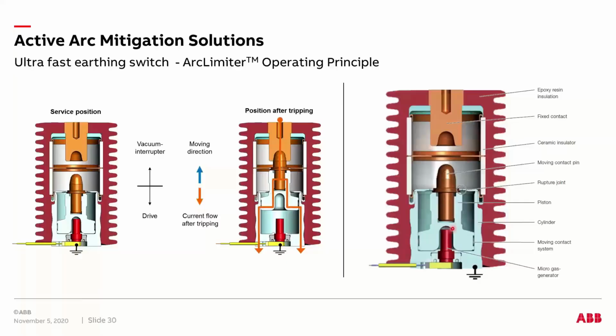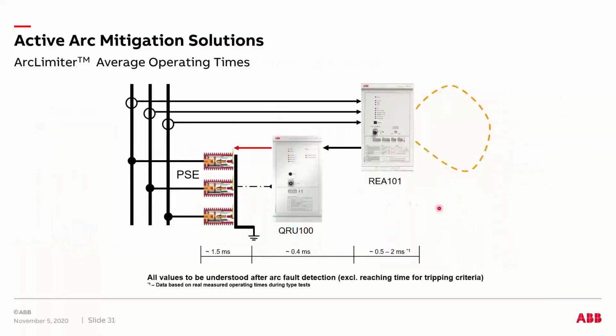to 1 millisecond, this particular connection gets connected to the top of the element, thereby grounding your bus bars to the ground, right? So this whole operation takes about 2 to 2.5 milliseconds once it gets a signal from the REA relay. So it is a typical setup where you have your REA relay, and you have your fiber optic loop running through your low voltage switchgear that is looking for a potential arc within your lineup.